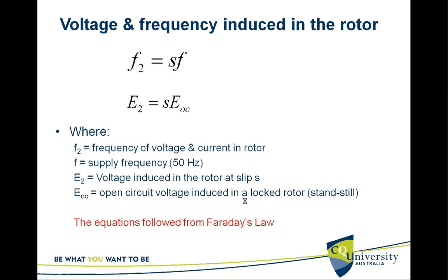When the rotor is at standstill, it is more like a three-phase transformer with a primary and a secondary, because there are two sets of three-phase windings — one in the stator and one in the rotor — and they do not move with respect to each other.